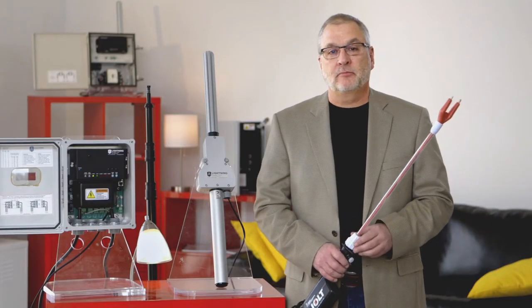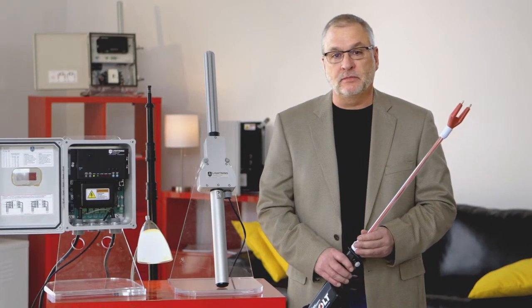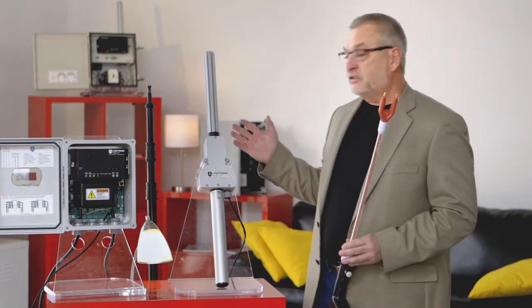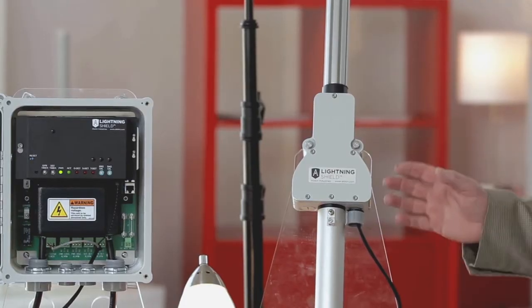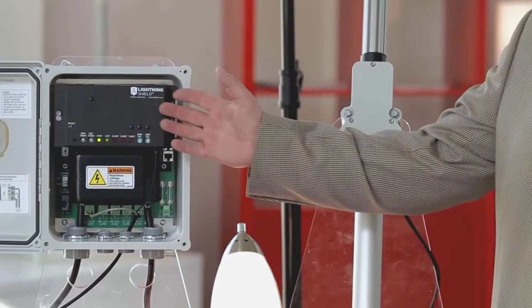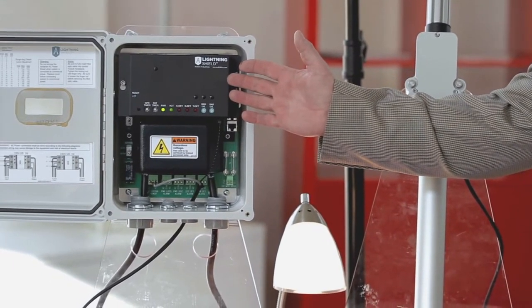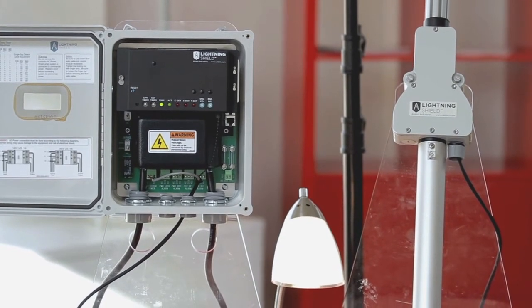When it comes to detecting a pending lightning strike, there's two components to Lightning Shield. Number one, we have the detector here. It sends a signal down a fiber optic cable into this control module, which then will open a contactor, and that contactor will isolate your sensitive equipment from lightning damage.